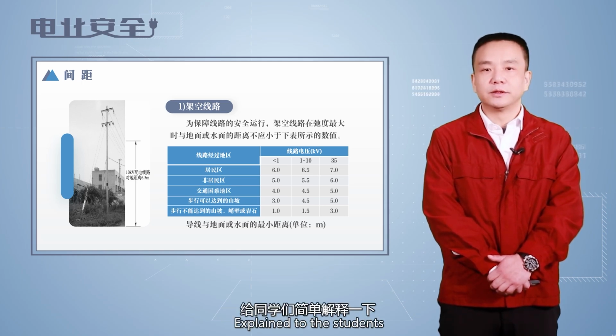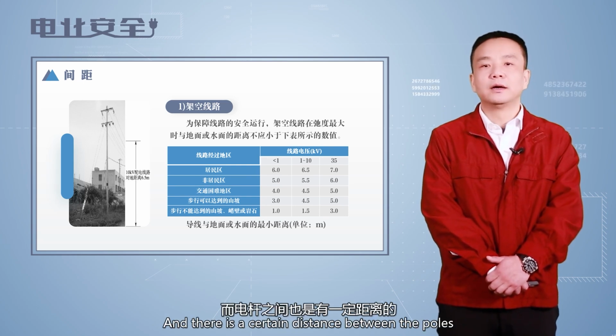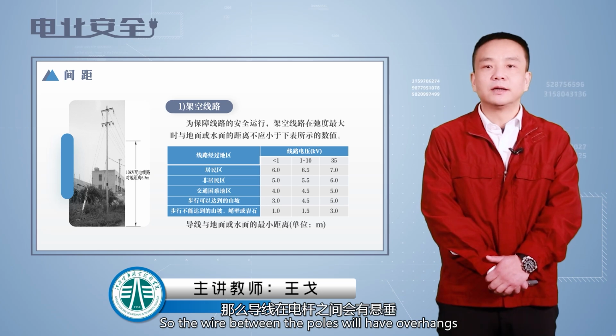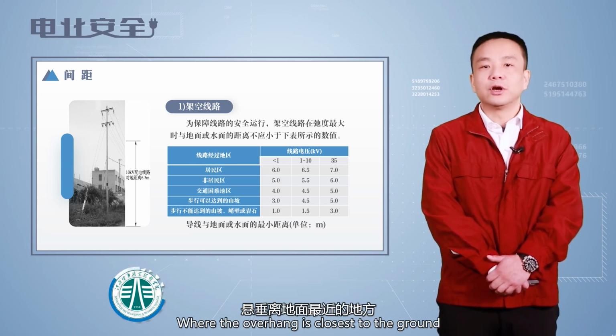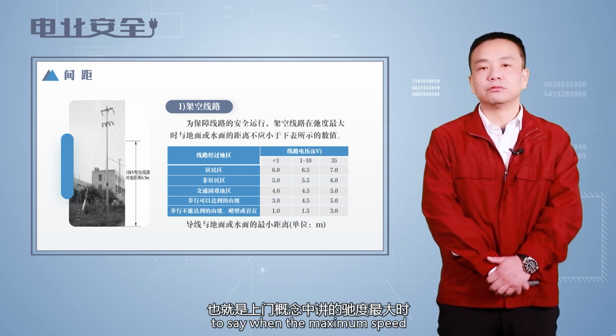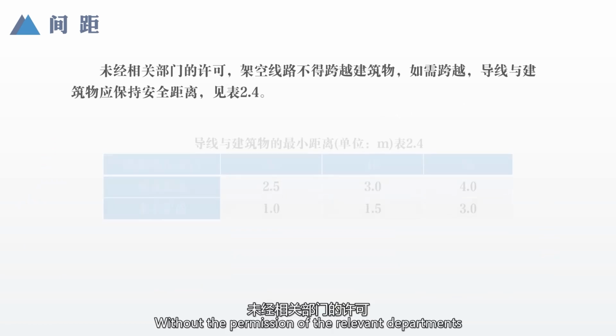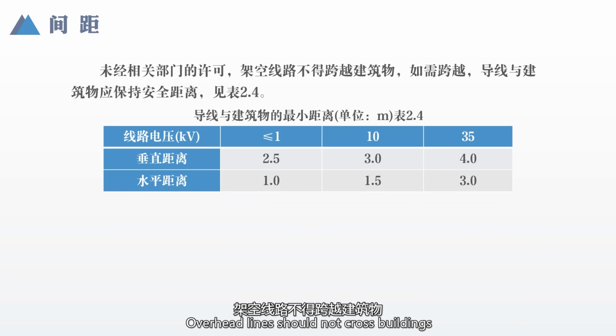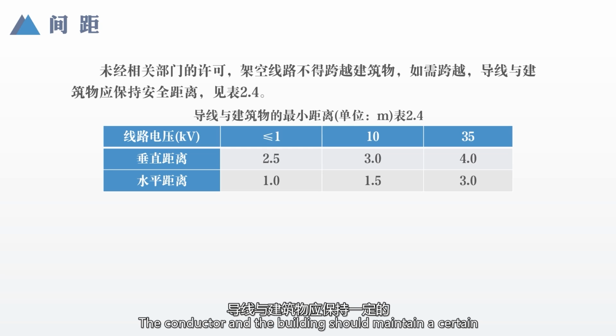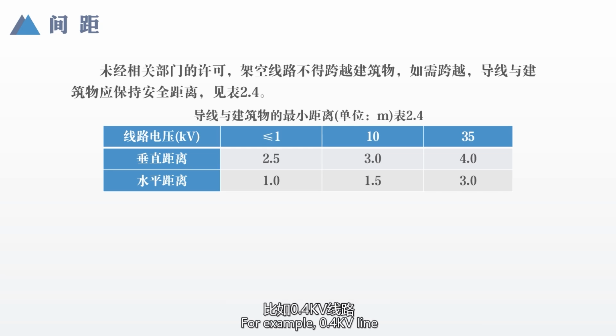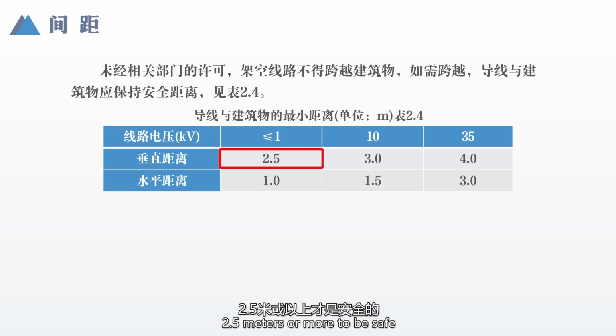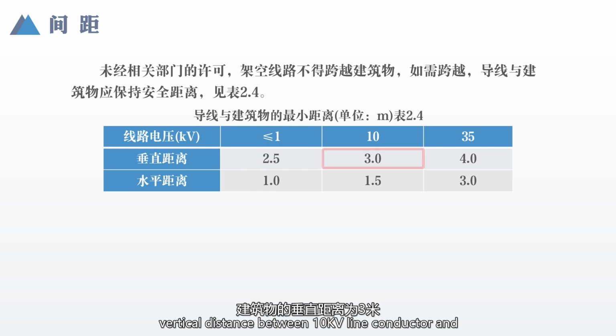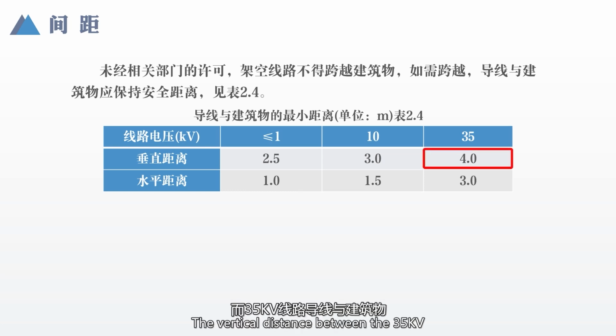I will explain the concept of sag to the students. Because the wires have a certain weight, and there is a certain distance between the poles, the wire between the poles will sag, and where the sag is lowest it is closest to the ground. That is the concept of maximum sag. For safety reasons, without the permission of the relevant departments, overhead lines should not cross buildings. If it is necessary to cross, the conductor and the building should maintain a certain safe distance. For example, for a 0.4 kilovolt line, the vertical distance between the conductor and the building is 2.5 meters or more to be safe. For 1 kV and 10 kilovolt line conductors, the vertical distance to the building is 3 meters or more to be safe. For a 35 kilovolt line conductor, the vertical distance to the building is 4 meters or above to be safe.